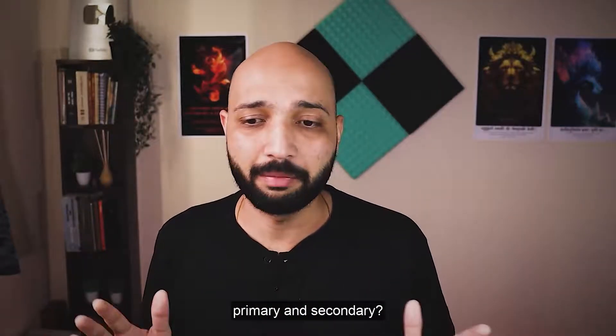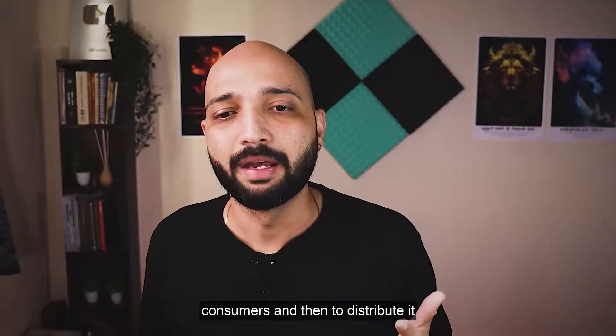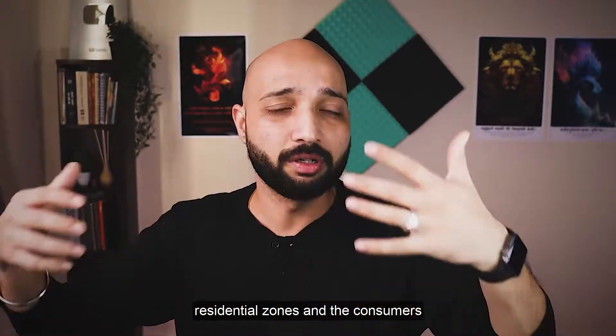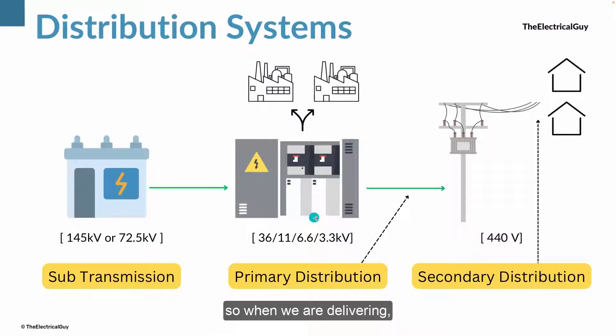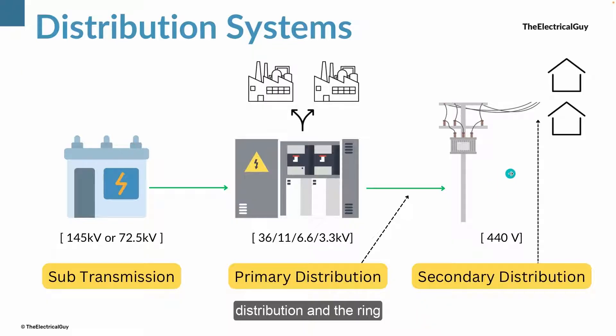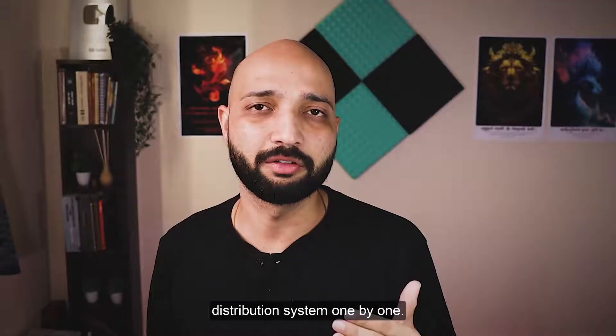Primary distribution is mainly used to supply high-voltage consumers and to feed the secondary distribution network. Secondary distribution delivers power to residential zones and consumers who need low-voltage power. When delivering 11 kV power to the secondary distribution system, there are two main methods used for primary distribution: radial distribution and ring main distribution. So when we say radial or ring main, keep in mind these relate to the primary distribution system.